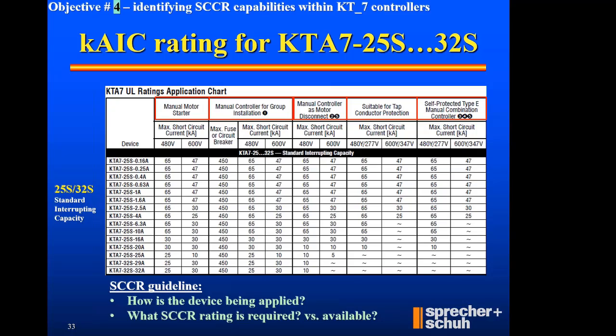Now I'm at the 600 Canadian perspective. As I get into the higher amps, I missed the boat on a 29A and a 32A. I've got to use something else down in the page, which is on the next slide or two. But okay, suitable for tap conductor protection. That doesn't come up very often, a very unusual circumstance, so we'll skip over that one.